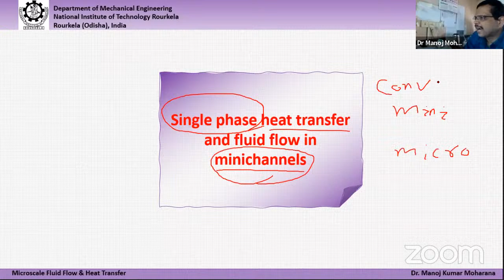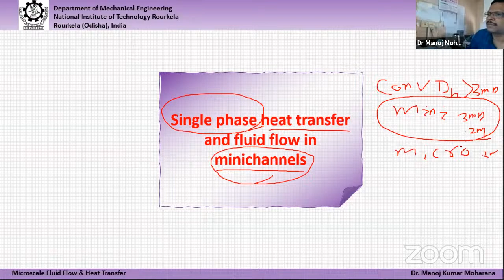We have a conventional channel, a mini channel, and a micro channel. A conventional channel has hydraulic diameter greater than 3 millimeters. A mini channel ranges from 3 millimeters down to 0.2 millimeters, and a micro channel is less than 0.2 millimeters or 200 micrometers.